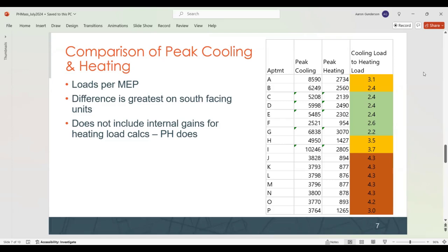So Lois, what's the implication of there being a big delta between the peak heating and the peak cooling? So what you're going to get is really bad efficiencies in the winter because we're going to be cycling and cycling and cycling, and it's going to hit these design loads, right, at the design point of the year. And so they're even smaller when you're not at the design point of the year. So you're in such an imbalance in these systems. This was a VRF system, right? And those have the smallest units in the apartments, right? So that's what we're dealing with. We need smaller equipment and we need better controls.